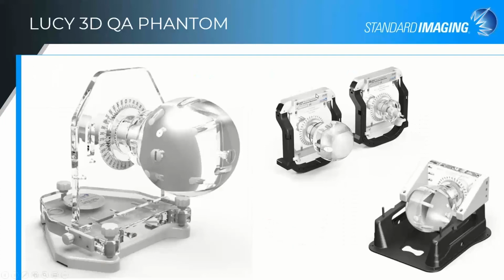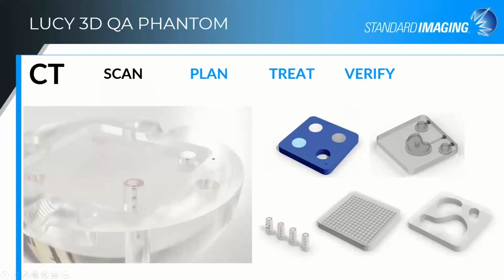I should say we have frames if people are still using frames for the different setup. Or the BrainLab maskless system, we have a very sleek way here of having this mount to the mask holder. There's also the dedicated holder for the Lucy Phantom that has a positioning base that fits on a Sivco lock bar, so it can be repeatedly positioned just on your couch as well. It's really designed for the full end-to-end testing, so scan, plan, treat, and verify.